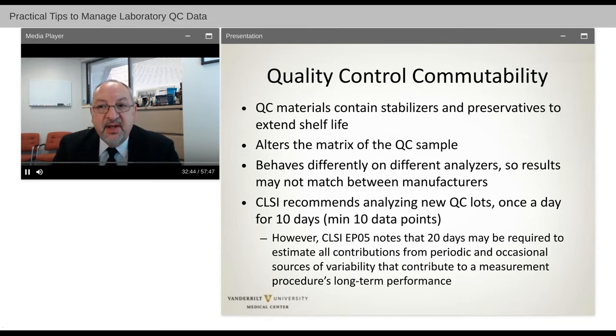So CLSI recommends analyzing new QC lots once a day at a minimum for 10 days. There's also EP05 that notes that 20 days of performance may be required to get a better estimate of all the different contributions from periodic and occasional sources of variability that contribute to a measurement procedure's long-term performance.